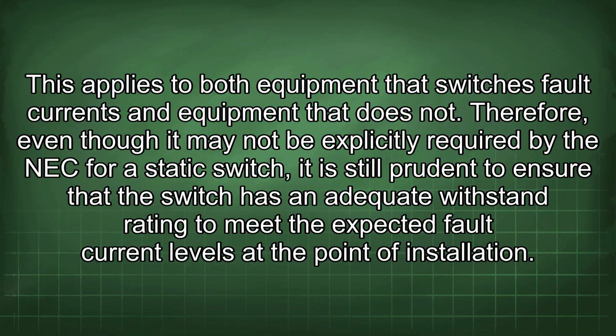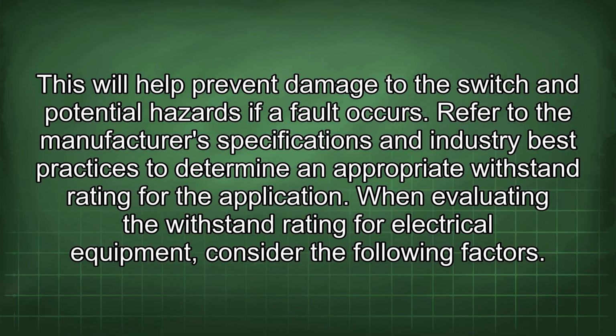Therefore, even though it may not be explicitly required by the NEC for a static switch, it is still prudent to ensure that the switch has an adequate withstand rating to meet the expected fault current levels at the point of installation. This will help prevent damage to the switch and potential hazards if a fault occurs. Refer to the manufacturer's specifications and industry best practices to determine an appropriate withstand rating for the application.